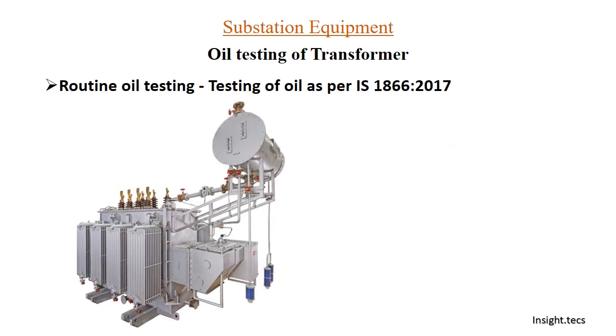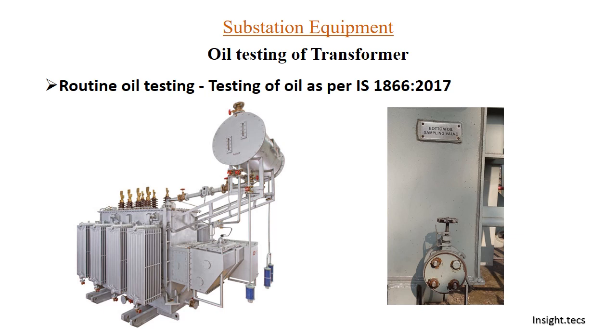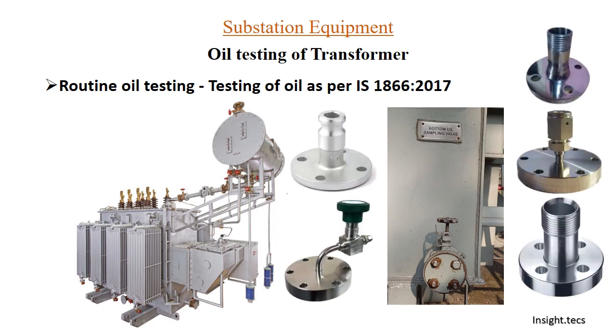Now let us understand how oil samples are taken from the transformer for routine oil testing. There is a bottom oil sampling valve present in the transformer — this kind of valve you can see in all transformers. Oil samples are generally taken from the bottom oil sampling valve. From this valve we connect a flange, and through a pipe we can take the sample. Various kinds of flanges are available in the market; whichever flange fits with this sampling valve, you can use that.